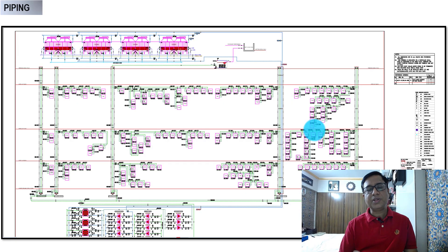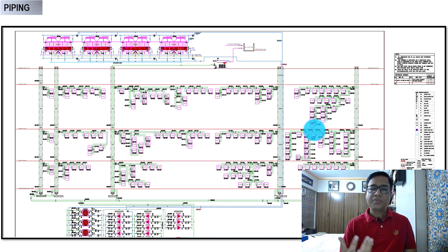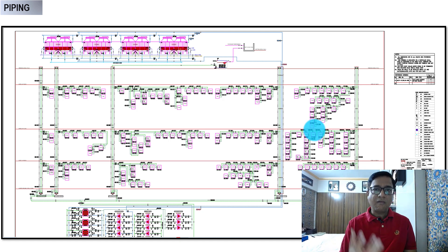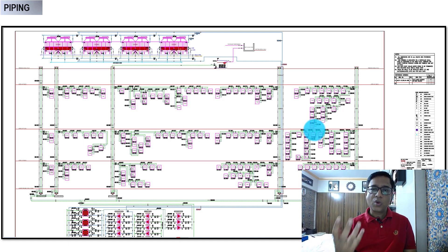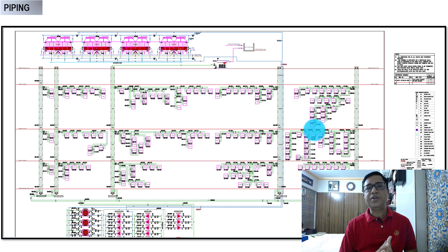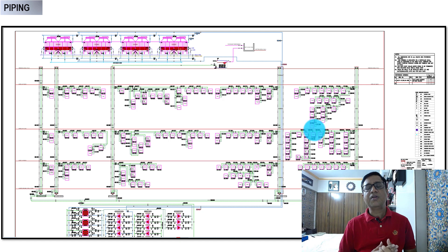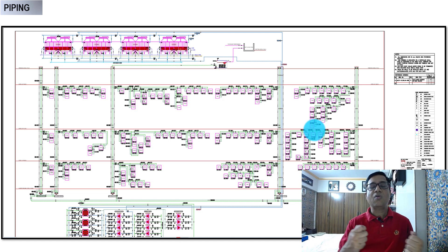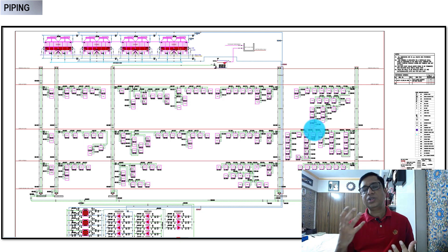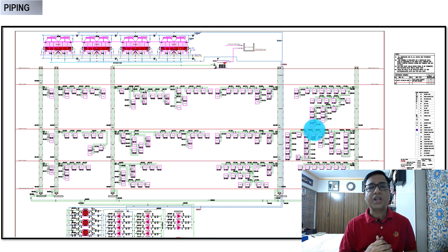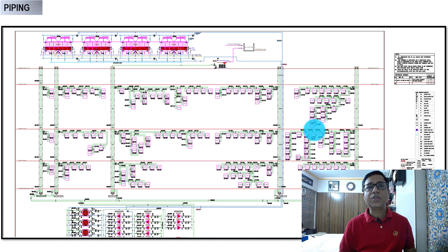For HVAC piping, the basic document we follow is the schematic — the chilled water schematic or condenser water schematic — which tells you what equipment is involved, what tappings are needed, what kind of valves and fittings are required to complete piping. It is not only about laying; it has to be properly managed in terms of valves, sensors, temperature gauges, and all other things you want to record and control. Balancing valves, non-return valves, strainers — everything comes in, and the schematic gives clarity of what needs to be done. This is the HVAC engineer's guide to move ahead with piping.